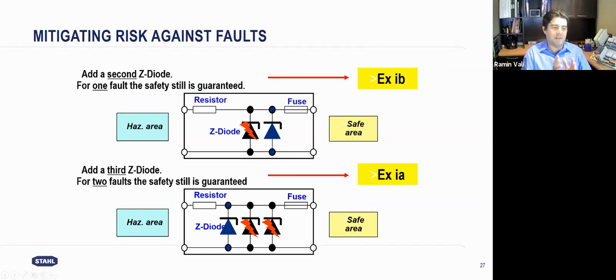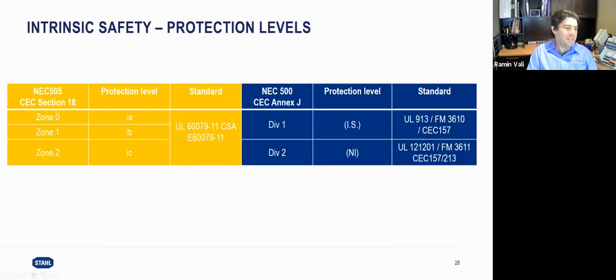Yeah, basically, these Zener diodes are an internal circuit of the barrier, right? So we are not choosing them. We choose an associated apparatus based on the area classification. Now, if we look at the next slide here, which has the table, I think we should go to the next. Yeah, here. We can see Ex ia field devices and associated apparatus, which have two levels of fault tolerance. And in a simple diagram, the previous one, it means it has three Zener diodes and can be installed in zone 0. So if we have a zone 0 area, we should use an Ex ia associated apparatus or Ex ia field devices.